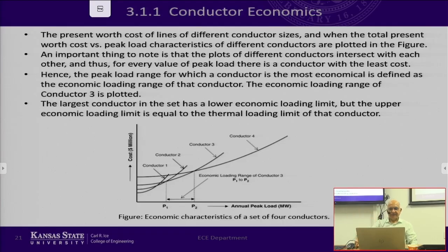So in this case, quality is not the issue. It is basically the fact that a bigger conductor is more expensive, so it has less losses. So you have these graphs right here. What we do is define what is called the economic loading range of each conductor. Conductor number 3, for example, has an economic loading range that goes from P1 to P2.